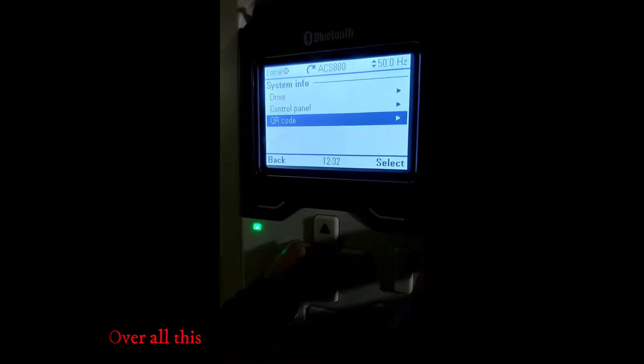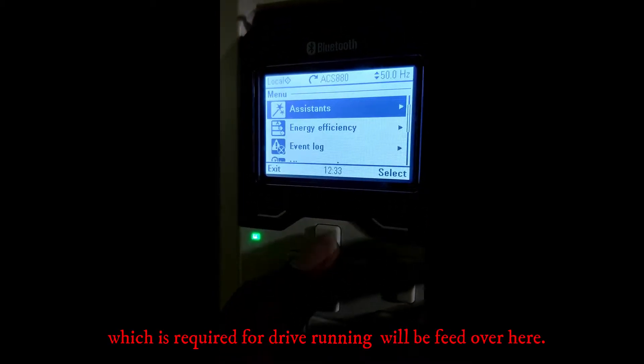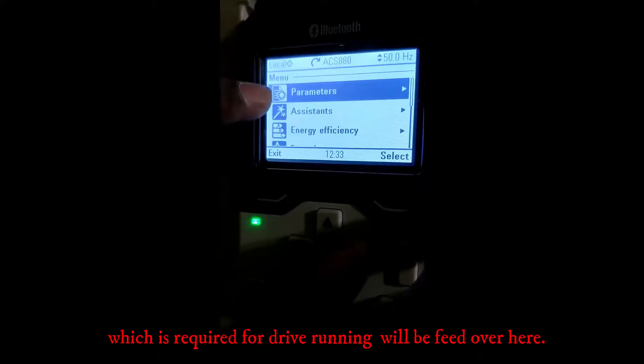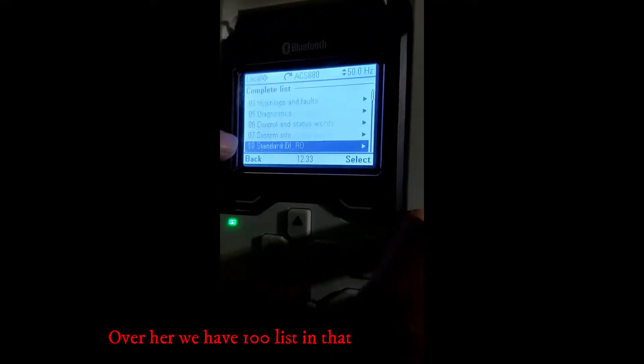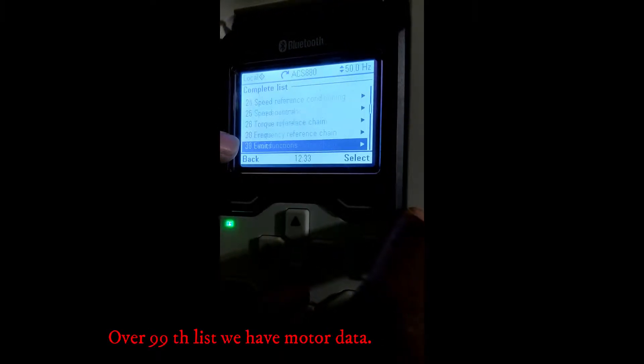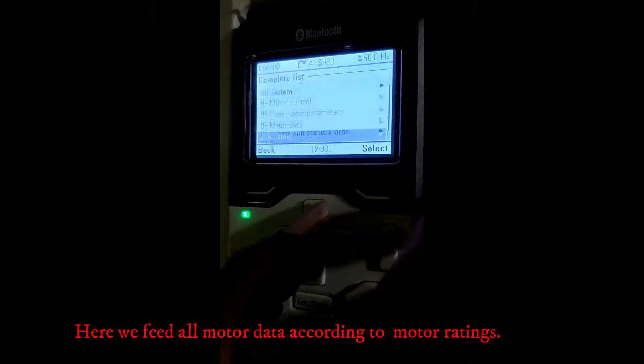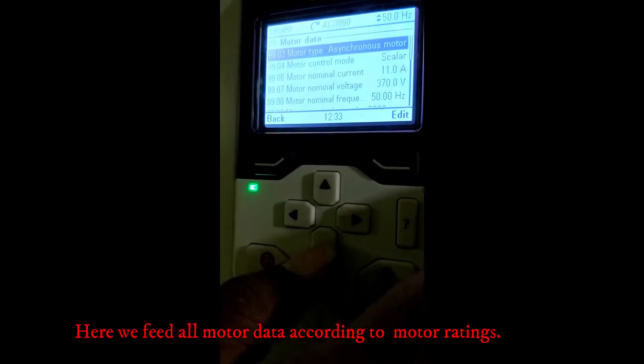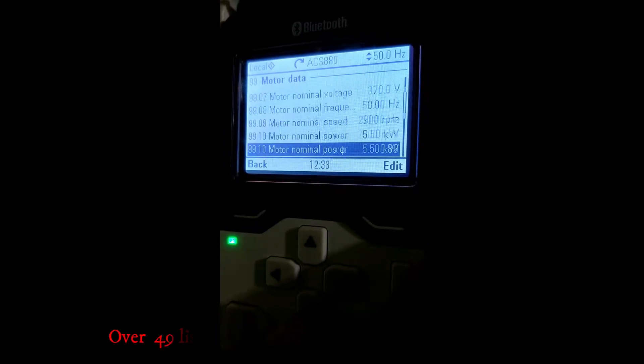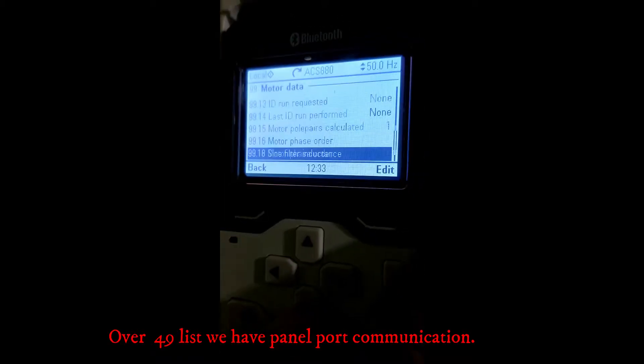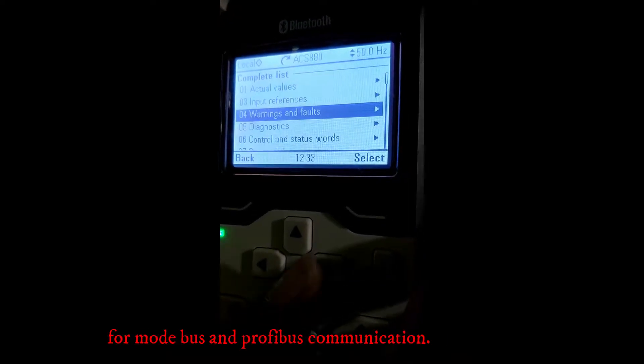Overall, the Parameter menu is very important because all the input data required for drive running is fed here. In the 99th list we have motor data — all motor data is fed here according to motor ratings and customer speed requirements. In the 49th list we have panel port communication, where we set the address ID and baud rate for Modbus and Profibus communication.